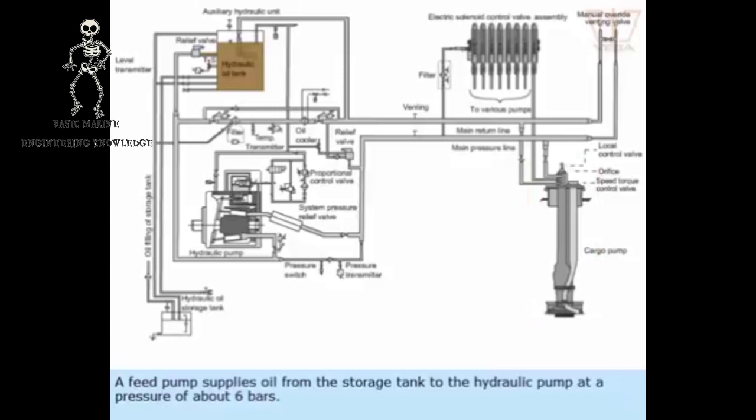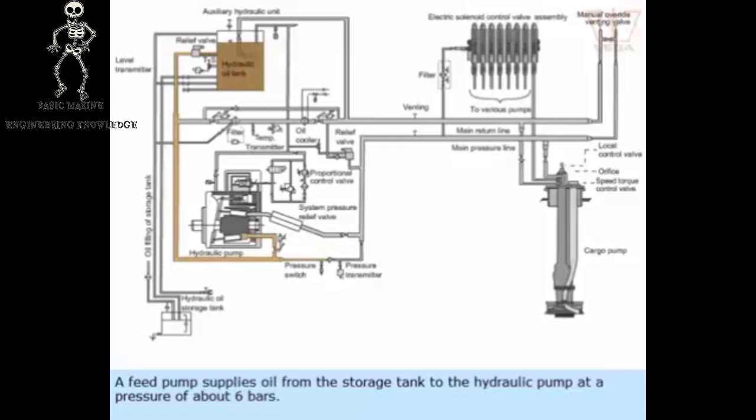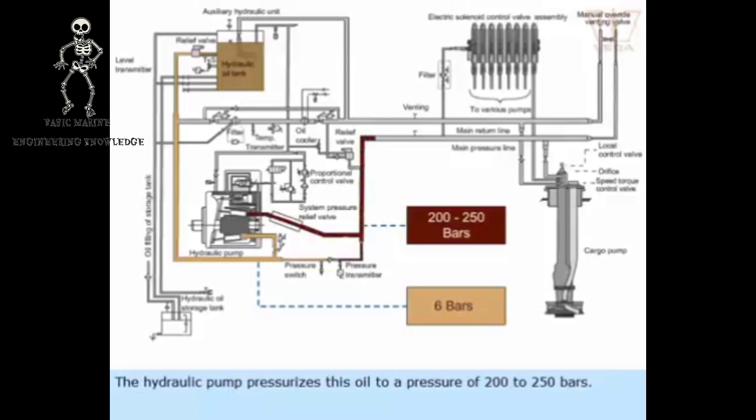A feed pump supplies oil from the storage tank to the hydraulic pump at a pressure of about 6 bars. The hydraulic pump pressurizes this oil to a pressure of 200 to 250 bars.